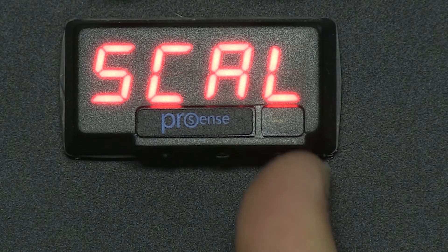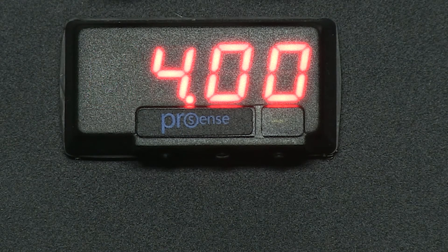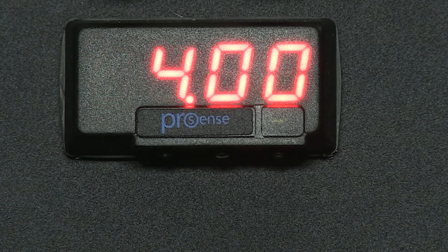I don't wish to scale in this setup so I will leave it at the default by pressing Enter. INP1 for input 1 and 04.00 displays. We are using a 4 to 20mA input so we leave this one alone. Press Enter and DSP1 displays with 04.00.